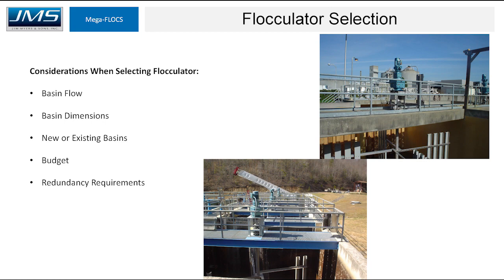The budget is another consideration, as certain technologies have a better flocculation per volume of water ratio than others. Another factor is redundancy requirements: some technologies allow one basin to be operated by one drive, while other technologies may have numerous drives per flocculation basin. Baffled wall-type flocculators have no drives at all.